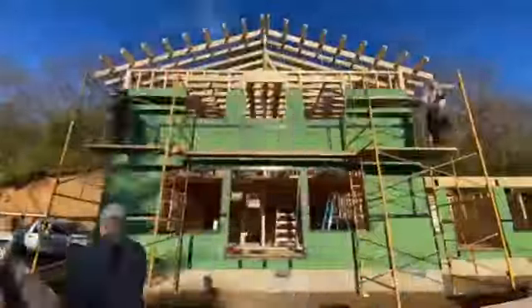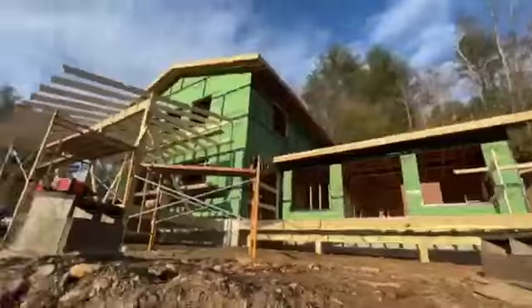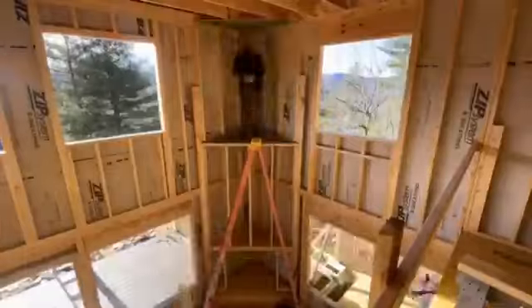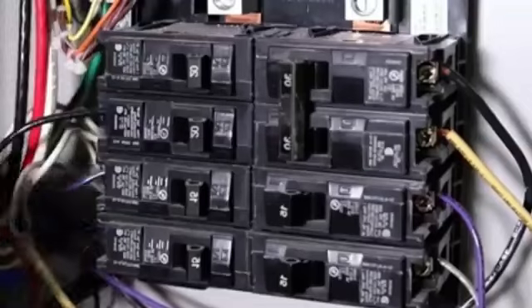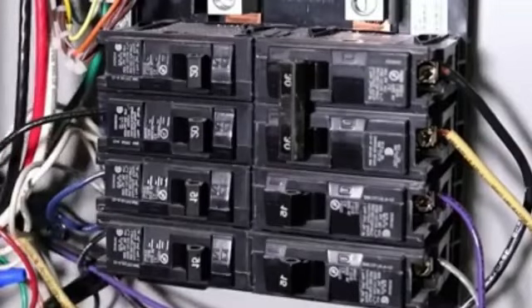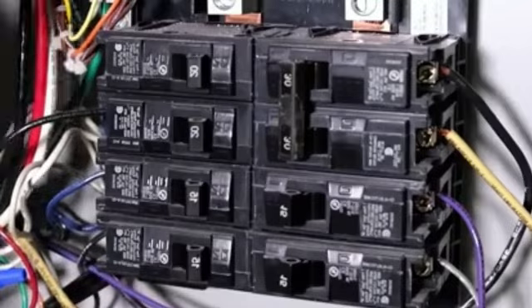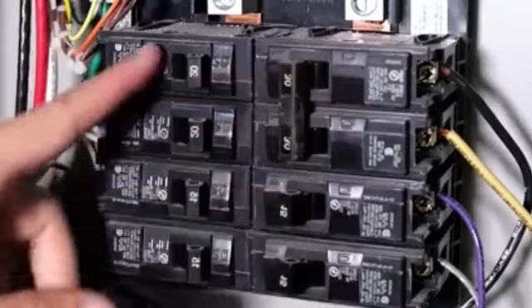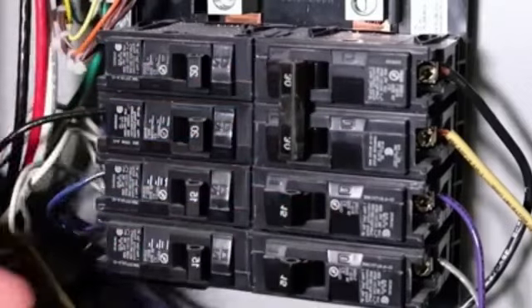Breakers cycling near their maximum rating generate heat. That heat radiates into the panel enclosure and degrades the bus bars, the thick copper or aluminum strips that distribute power to each breaker. Degraded bus bars develop high resistance connections. High resistance connections generate more heat, thermal runaway inside your electrical panel. You do not see it happening. The panel cover hides everything. The breakers do not trip. They are working exactly as designed. But the panel box becomes warm to the touch.